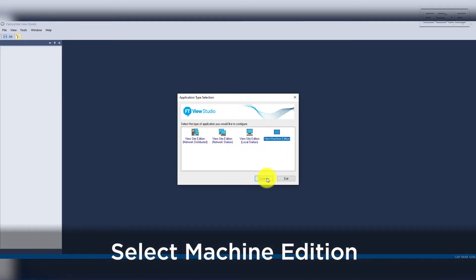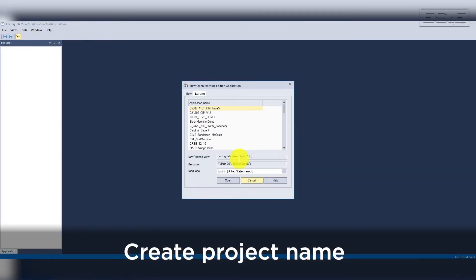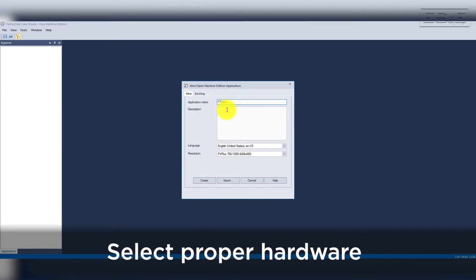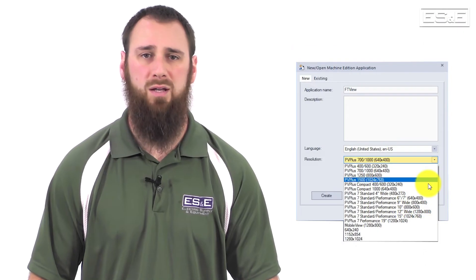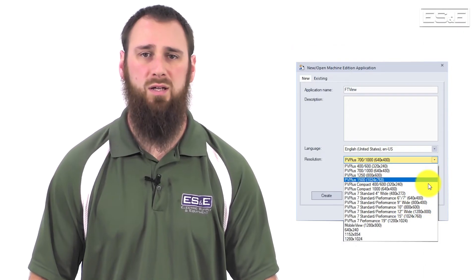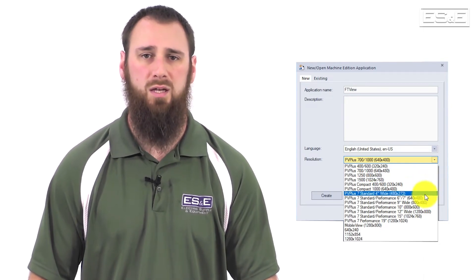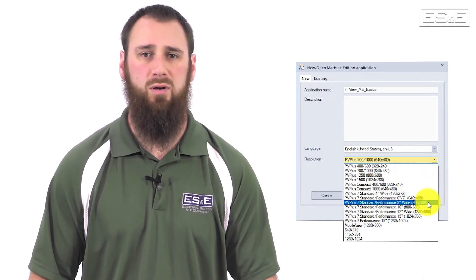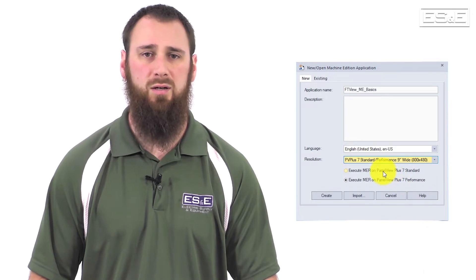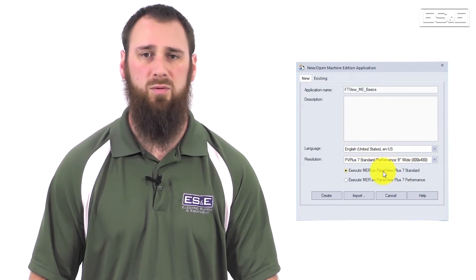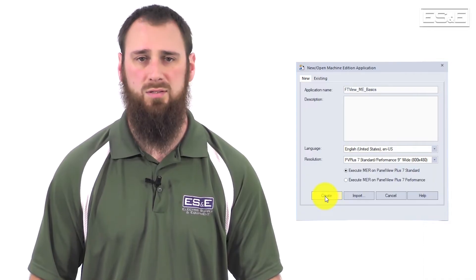Once you select ME, you give it the project name and select the proper hardware. Keep in mind, the Panel View Plus 7 has two versions, so it is important to select the proper one. If you do pick the wrong one, you can change it later, but it may cause issues if your project exceeds the standard version limitations.